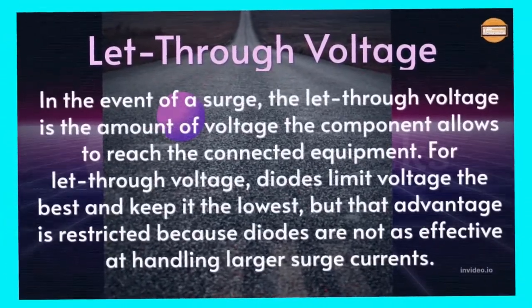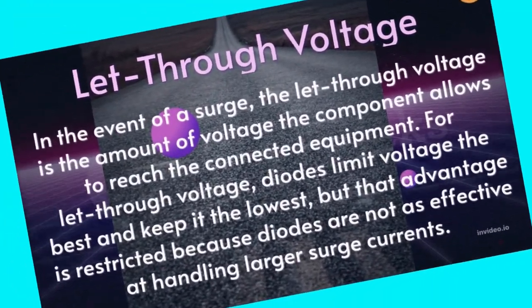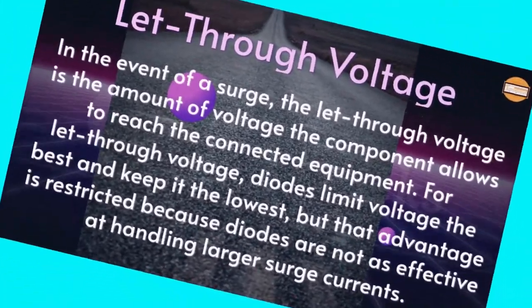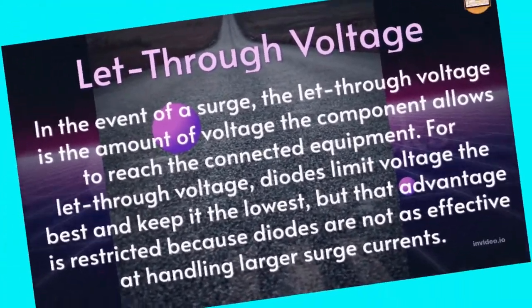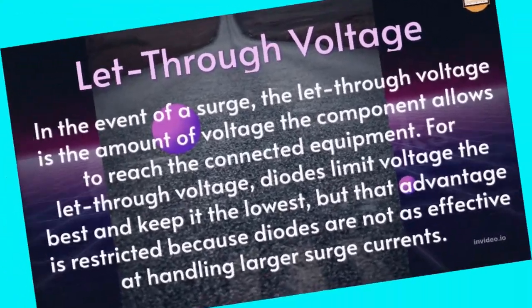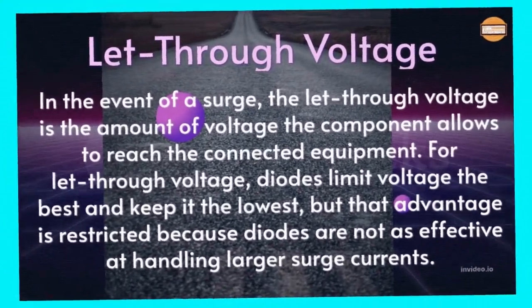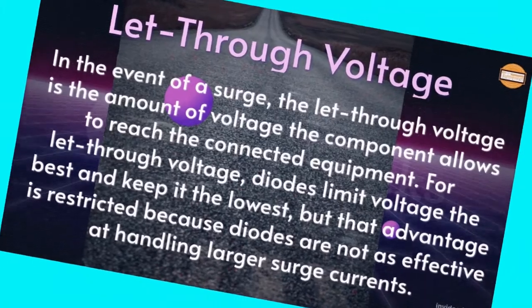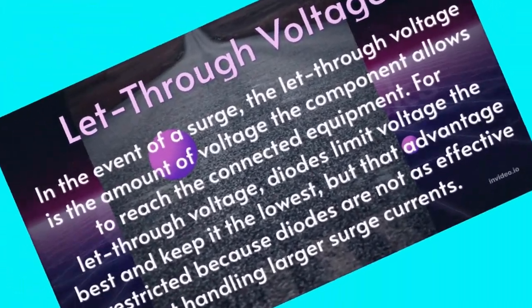Let-through voltage: in the event of a surge, the let-through voltage is the amount of voltage the component allows to reach the connected equipment. Diodes limit voltage the best and keep it the lowest, but that advantage is restricted because diodes are not as effective at handling larger surge currents.